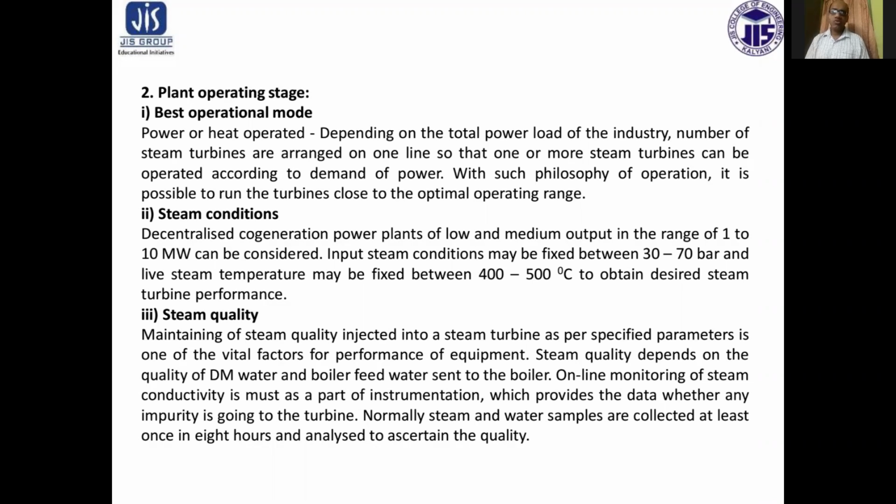Number 3, steam quality. Maintaining the quality of steam injected into a steam turbine as per the specified parameters is one of the vital factors for performance of equipment. Steam quality depends on quantity or quality of demineralized water, that is DM water, and boiler feed water sent to the boiler.